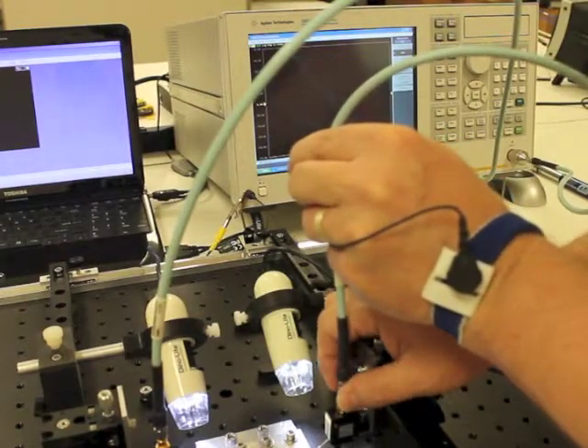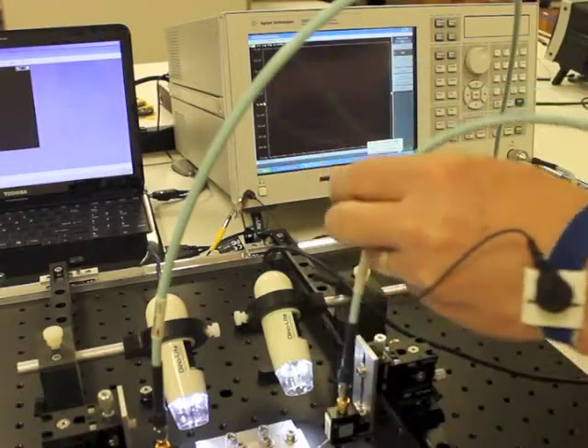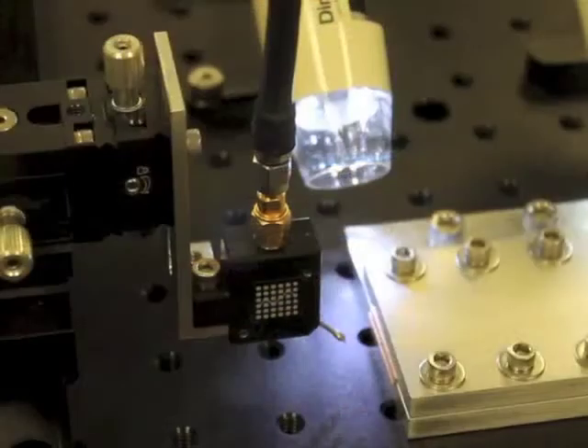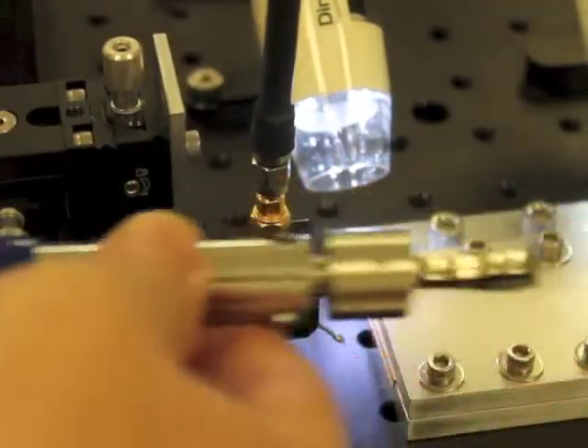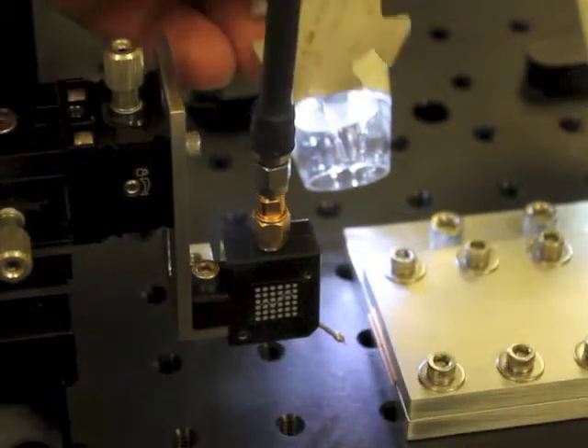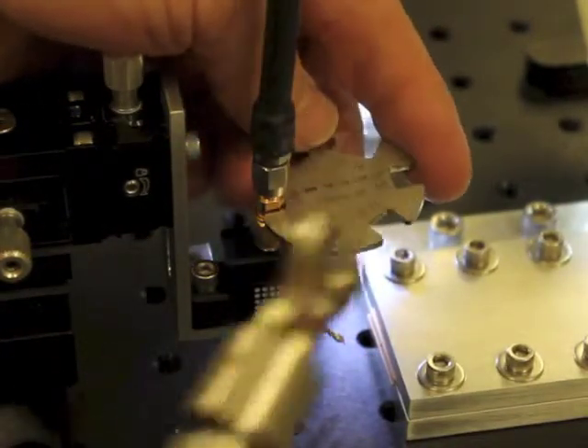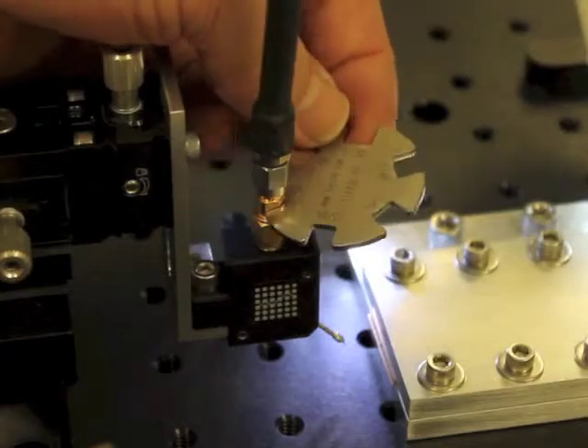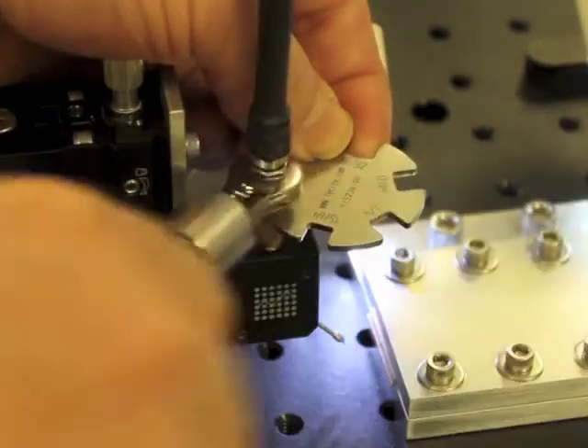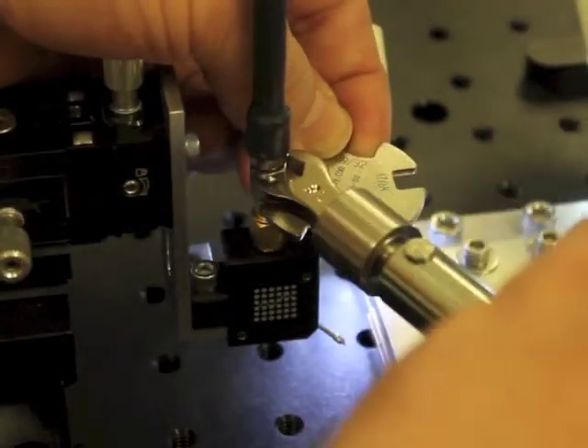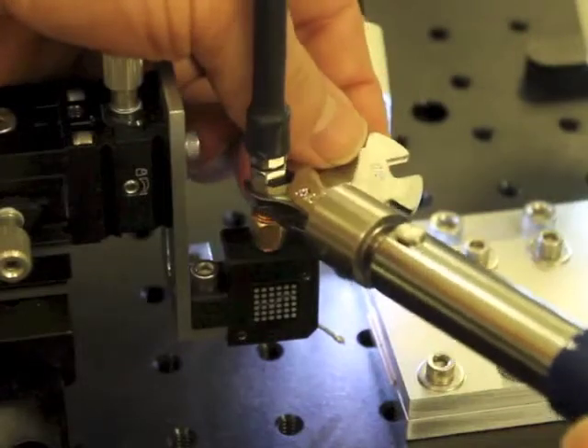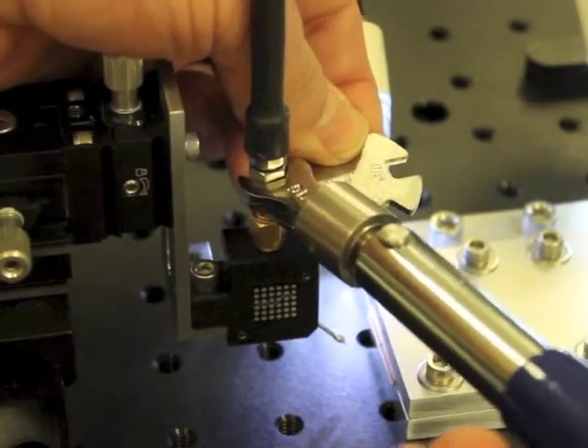After we hand tighten the SMA connectors on both the left and the right probes, we're going to use a torque wrench to make sure that we have a good electrical connection to the probe. We use a wrench to hold the connector on the probe so that it won't move, and then we tighten the SMA on the port 1 cable. This torque wrench will pop out at the desired torque, like that.